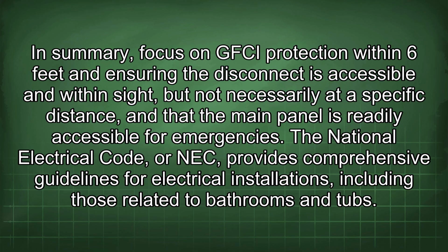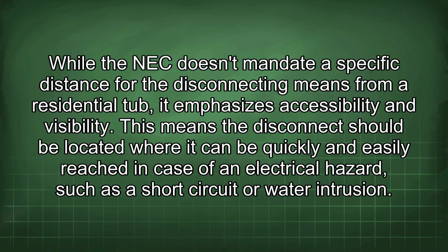The National Electrical Code, or NEC, provides comprehensive guidelines for electrical installations, including those related to bathrooms and tubs. While the NEC doesn't mandate a specific distance for the disconnecting means from a residential tub, it emphasizes accessibility and visibility. This means the disconnect should be located where it can be quickly and easily reached in case of an electrical hazard, such as a short circuit or water intrusion.